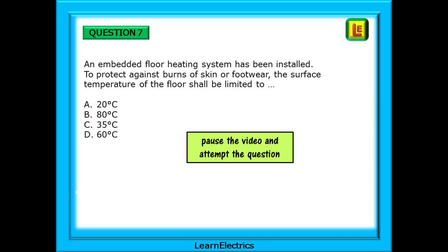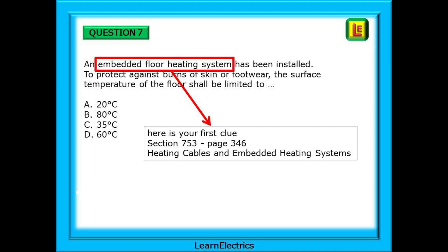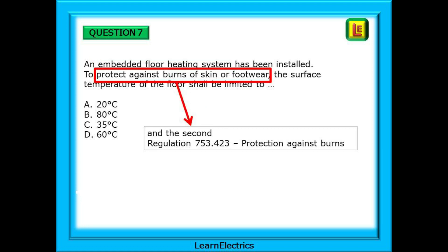Question 7 is next: An embedded floor heating system has been installed. To protect against burns of skin or footwear the surface temperature of the floor shall be limited to... and 4 possible answers. Here is the first clue from the question: Embedded floor heating system. Page 3 main contents will show this to be section 753 and it directs you to page 346. Your second clue is the phrase 'Protect against burns of skin and footwear.' Regulation 753.423 says Protection against burns and there is your answer.